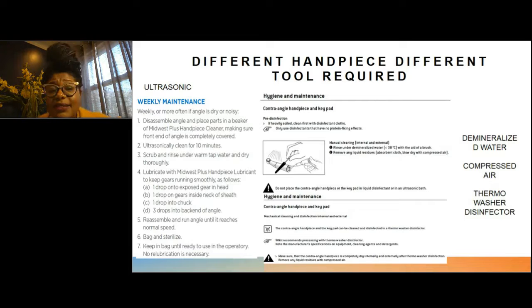Now, if you look at the one that says weekly maintenance on a weekly basis for a handpiece, it's asking you to ultrasonically clean it for 10 minutes. This excerpt is coming from after disassembling the head of a contra angle. It is asking on a weekly basis that the head is placed into an ultrasonic for 10 minutes. This manufacturer IFU actually even tells you the length of time it's supposed to stay within the ultrasonic.